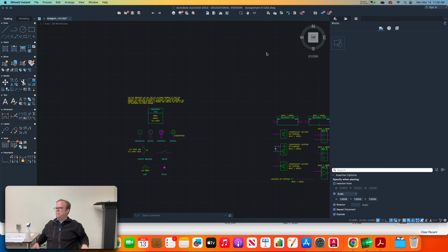And generally speaking, they go more than that, right? The sum total of the breaking capacity of each individual breaker is not going to equal 100 amps. It's going to be more than that. The theory is that you're not ever going to be pulling the full capacity of every single breaker in that panel. Part of the reason for that is that those individual breakers are hopefully going to start tripping when you start pulling more. You're never going to see that full 100 amps, hopefully. But you'll have more potential for current than the 100 amps in that panel.